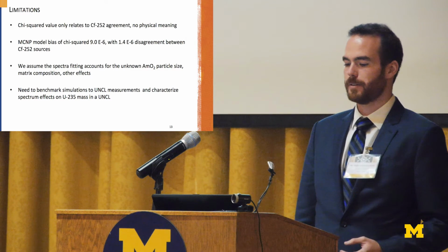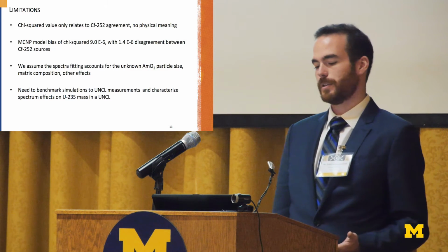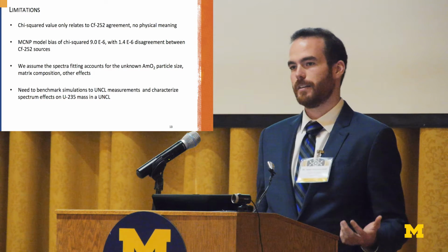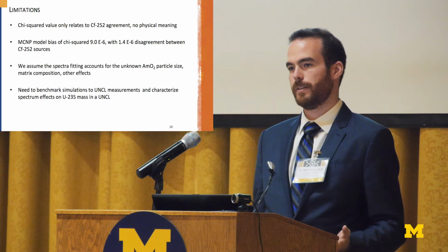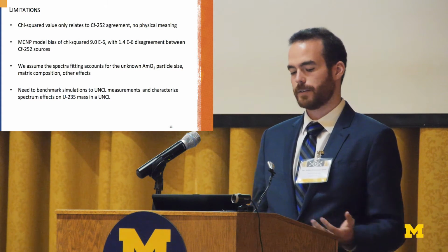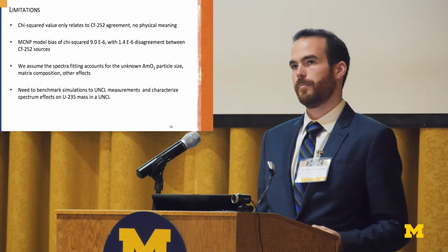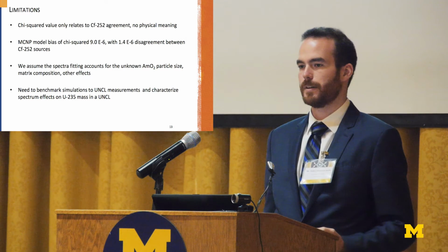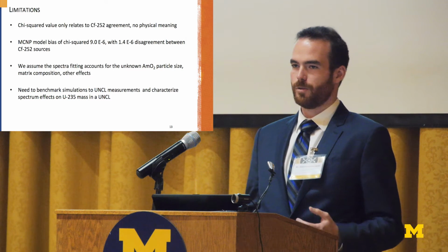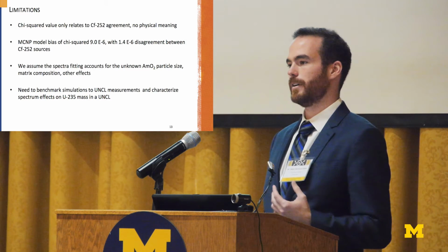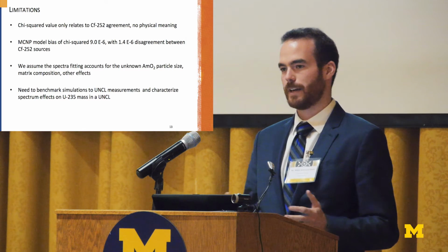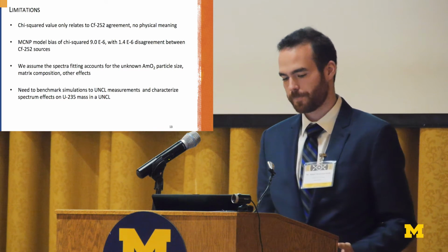And so we assume that the spectra fitting accounts for all of these unknowns that we talked about, the different particle sizes, the different matrix compositions, any effects that we are unaware of. Maybe the encapsulation of the source is not as well known as we think, anything else that we haven't thought of. And so, yeah, basically there's no way to really know these things without cutting a source open, which is obviously very impractical. And so we are calibrating our analytic source to these measurements and assuming that the calibration accounts for all of these effects.